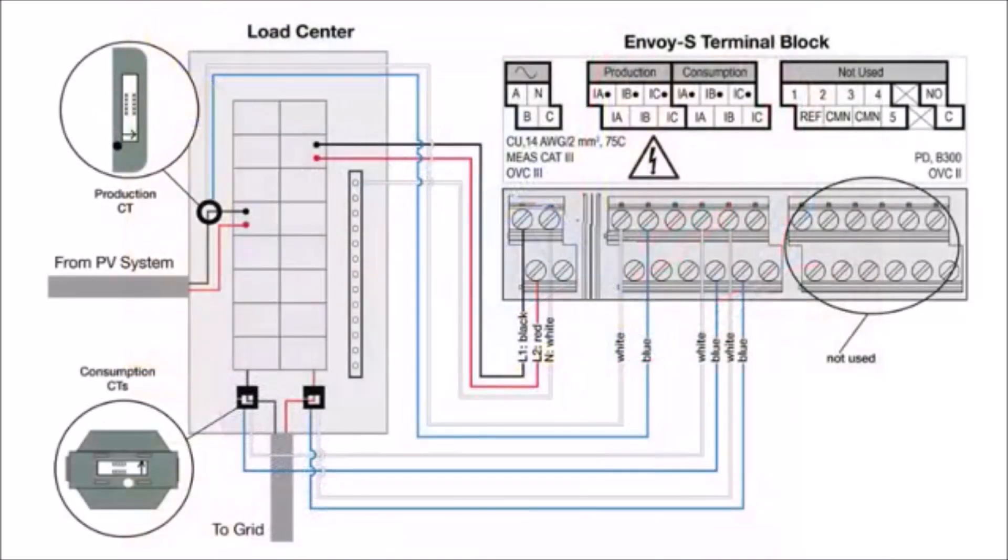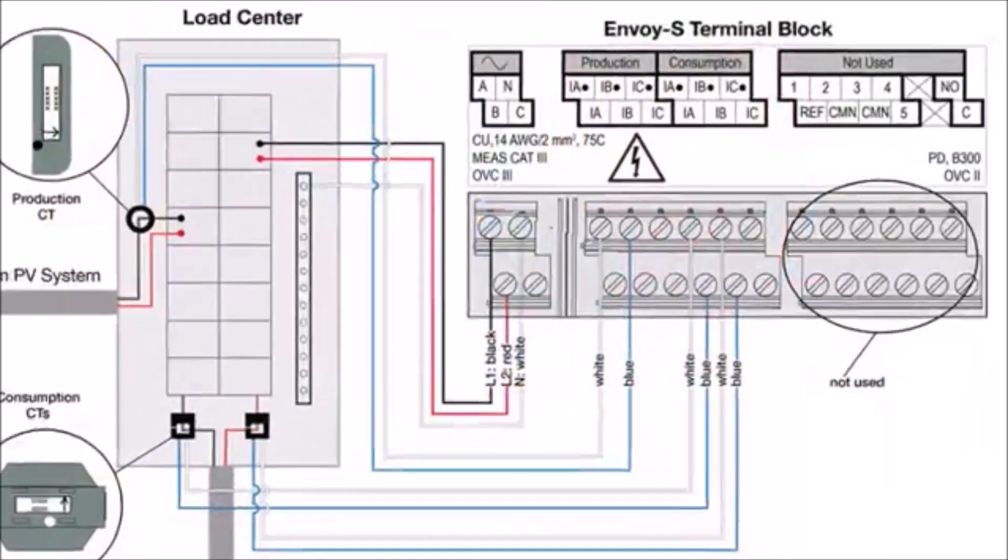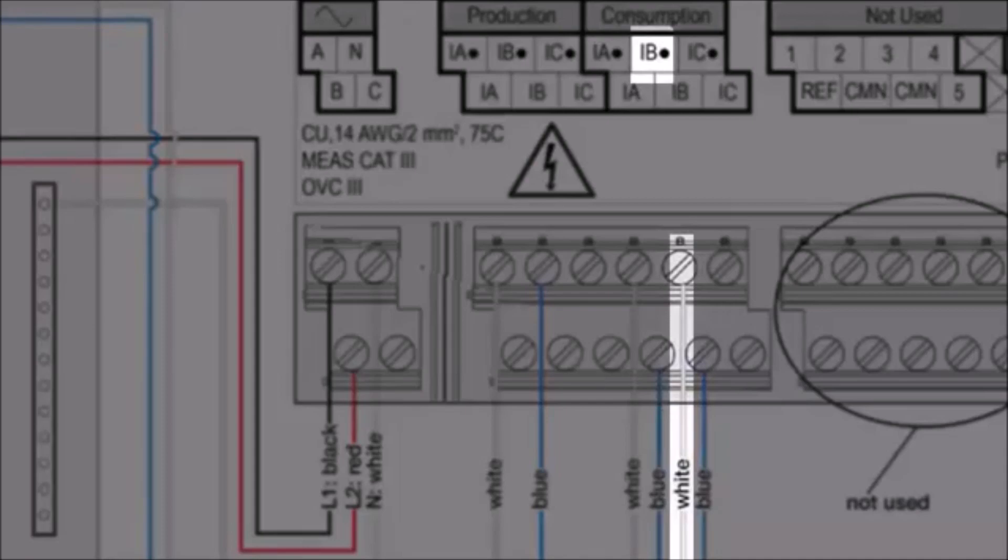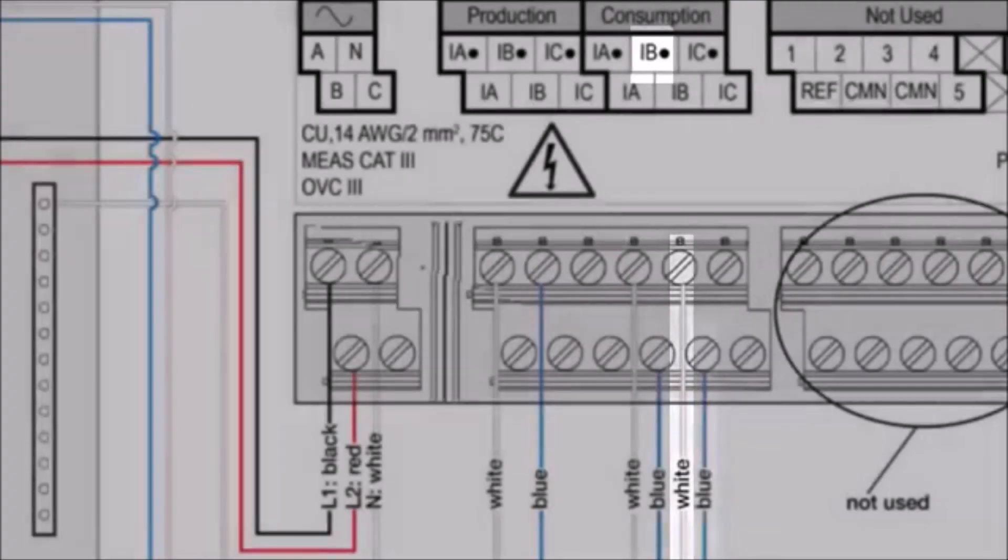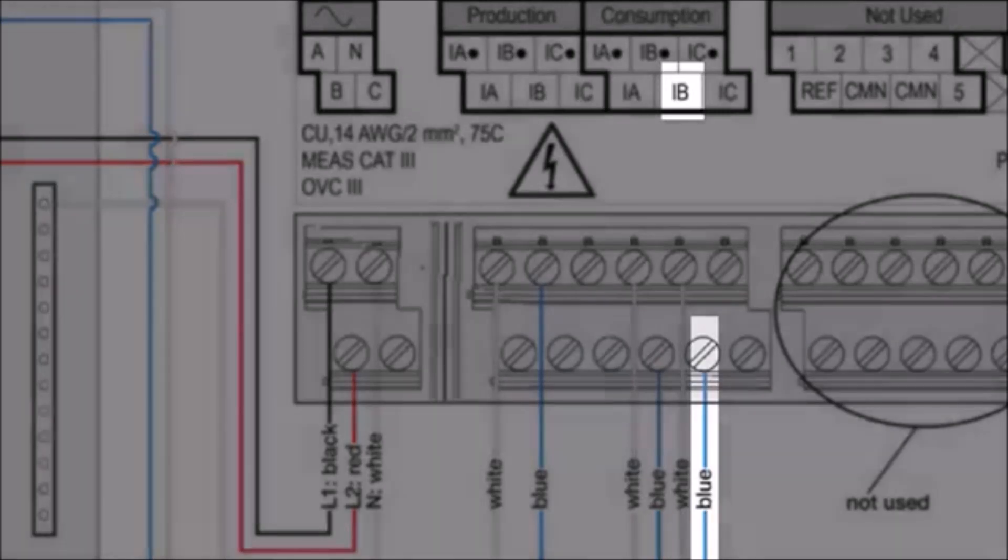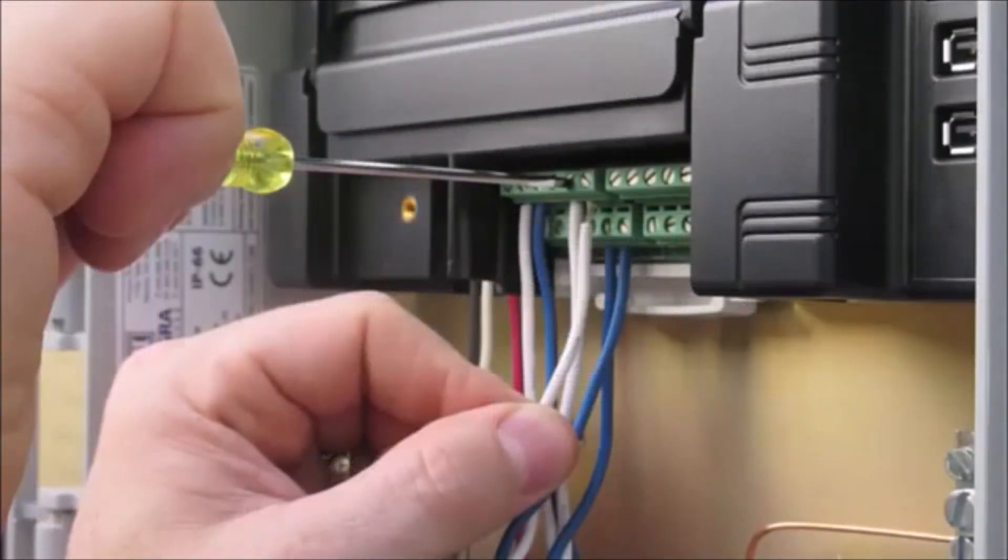For the unmarked CT wires, connect the white wire to the line 2 I-B dot terminal and the blue wire to the line 2 I-B terminal. Tighten all terminal block connections to 5 inch pounds.